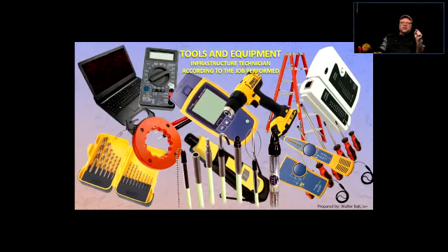So then, just to make sure that this is actually the pair, not a bleed through from another pair, you can connect a couple of wires to it. Sometimes, if it's a BIX, there's something called BIX clips. You can see them in the BIX presentation that I did, and you clip onto that and you short that pair. Once you short that pair, the tone should disappear because you just shorted it, right?